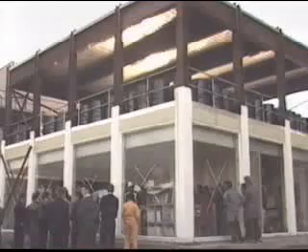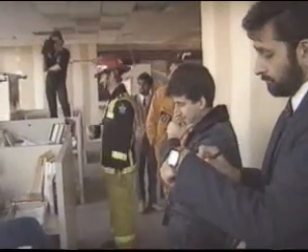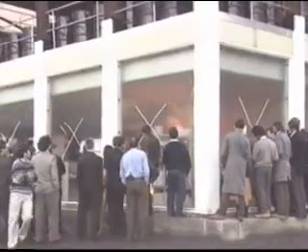The purpose of tests 3 and 4 was to study the development of fires which are not controlled by the automatic operation of sprinklers. The automatic sprinkler system was therefore turned off. The fire was started in a plastic waste paper bin partially under a workstation in the open plan area of the building. The smoke detector operated 5 minutes and 45 seconds from ignition.